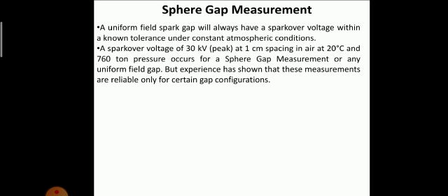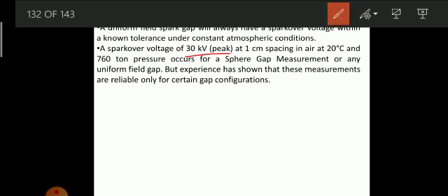A spark over voltage of 30 kilovolt peak occurs at 1 centimeter spacing in air at 20 degrees centigrade and 760 torr pressure, for a sphere gap or any uniform field gap. But experiments have shown that these measurements are reliable only for certain gap configurations. There is a limit of gap configuration. We cannot exceed the gap length more than the pre-specified value, as above it gives you a wrong measurement.